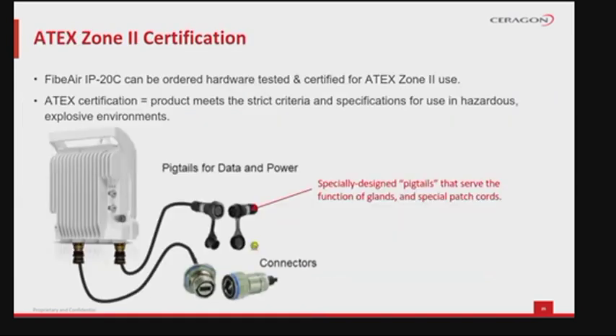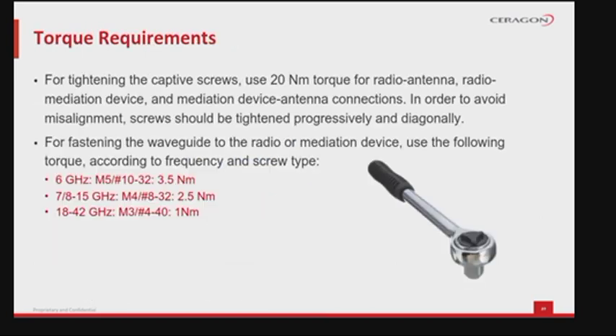The FibeAir IP-20C can also be ordered hardware tested and certified for ATEX Zone 2 use. ATEX certification means that the product meets the strict criteria and specifications for use in hazardous, explosive environments. For tightening the captive screws, use 20 Newton-meter torque for radio antenna, radio mediation device, and mediation device antenna connections. In order to avoid misalignment, screws should be tightened progressively and diagonally. For fastening the waveguide to the radio or mediation device, use the red marked notes in this slide which show the required torque, according to frequency and screw type.